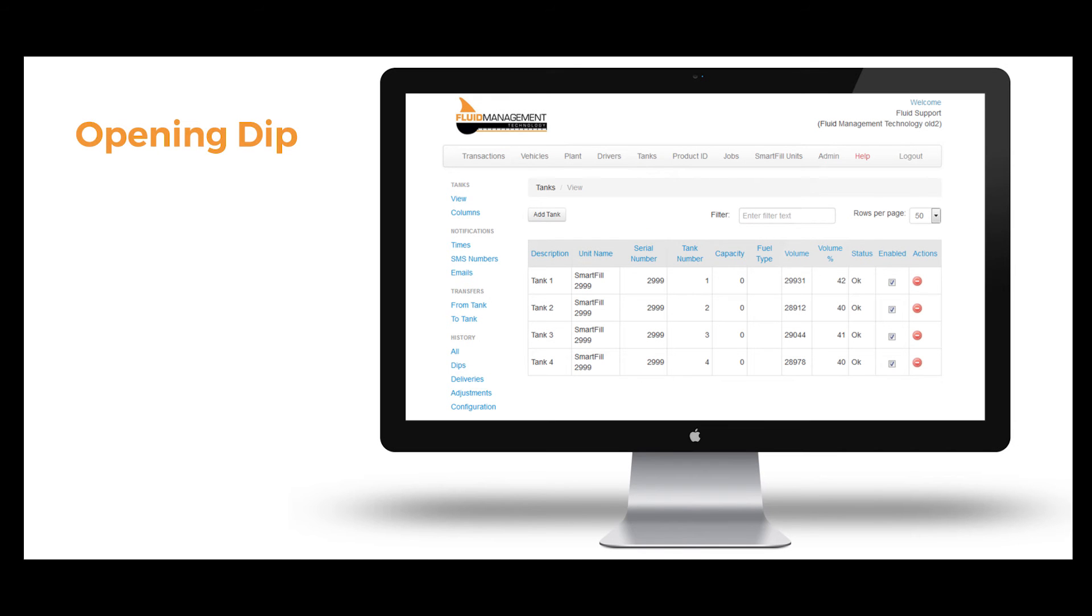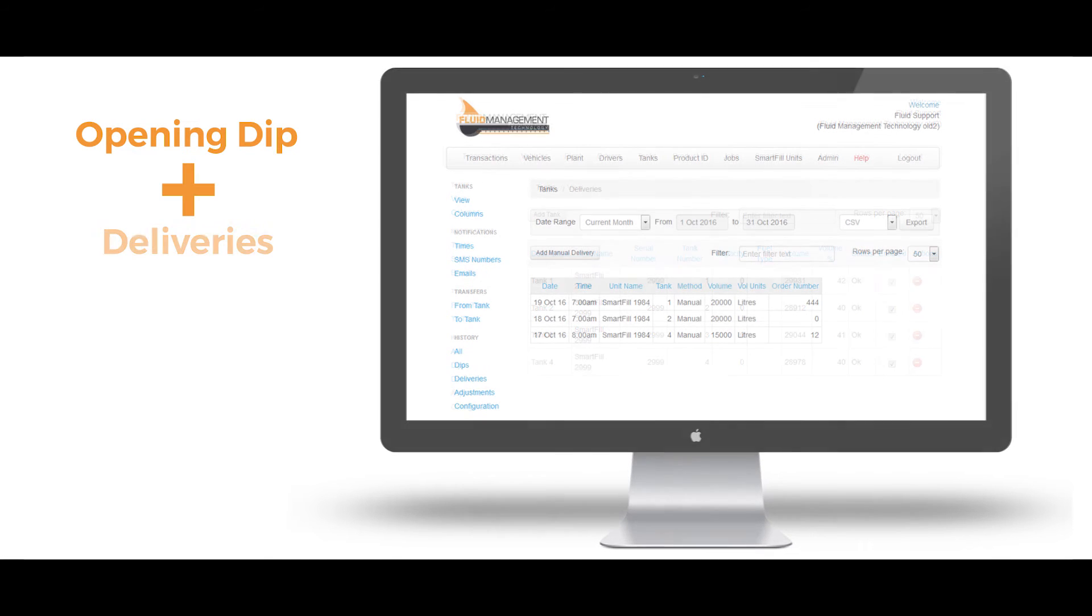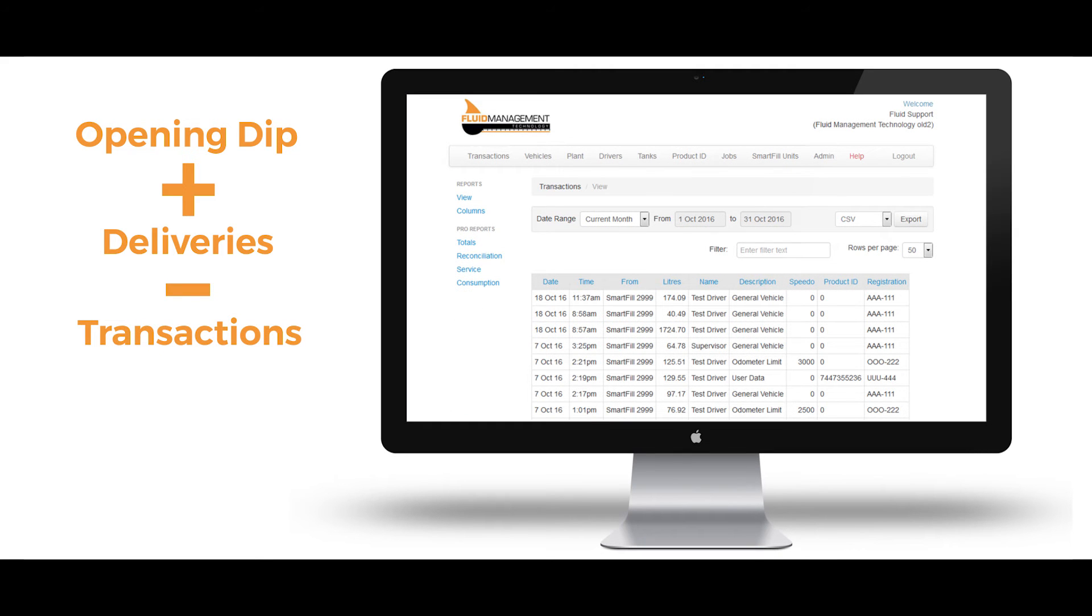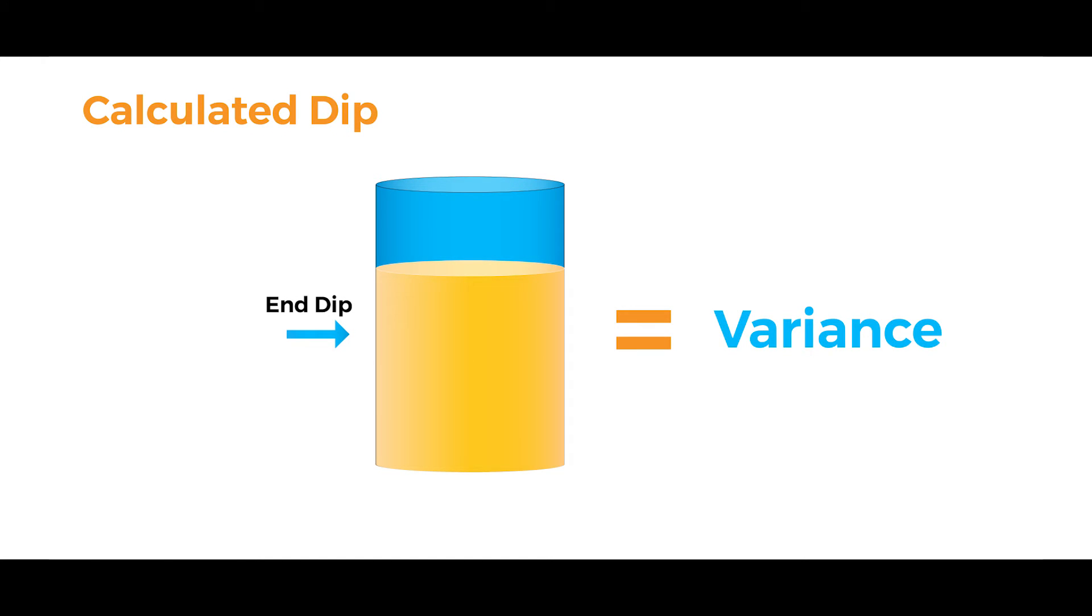The opening dip plus deliveries minus transactions equals calculated dip. The difference between the calculated dip and closing dip is the variance for the report time frame.